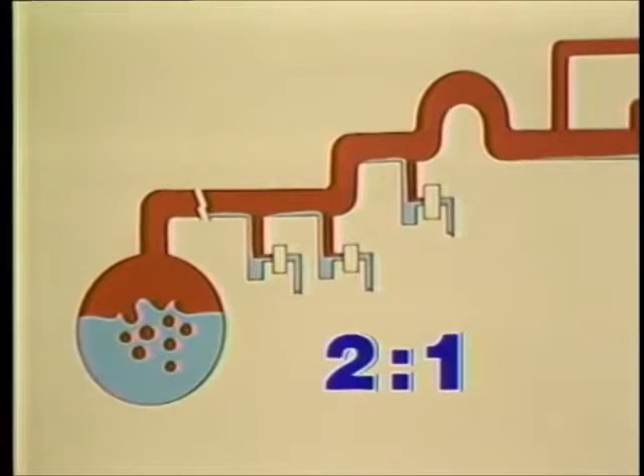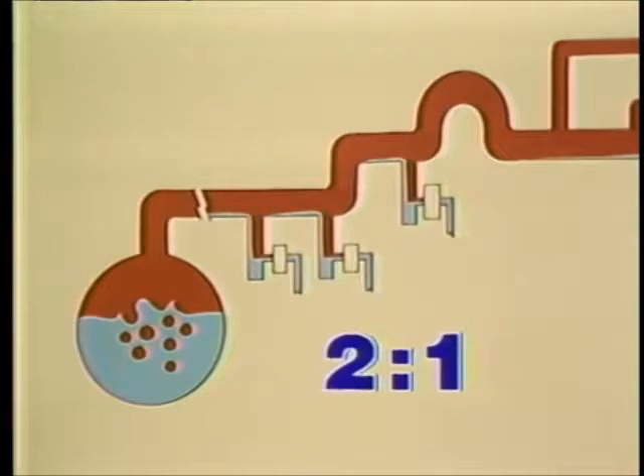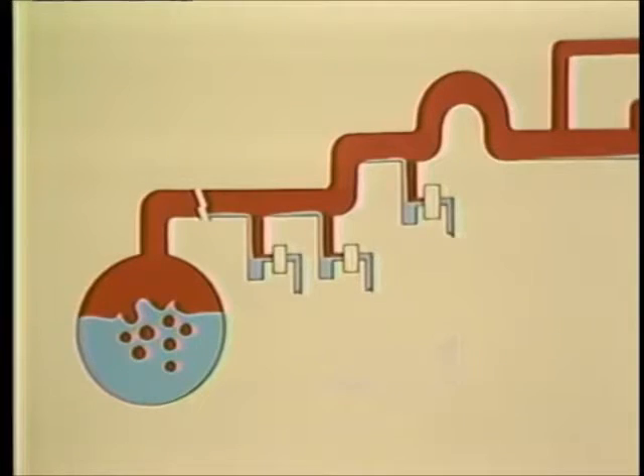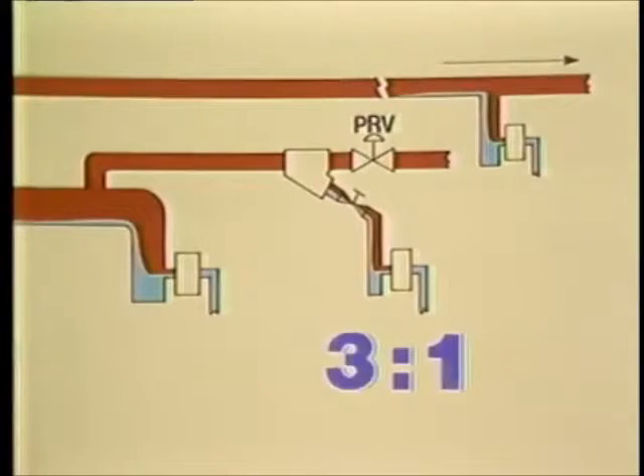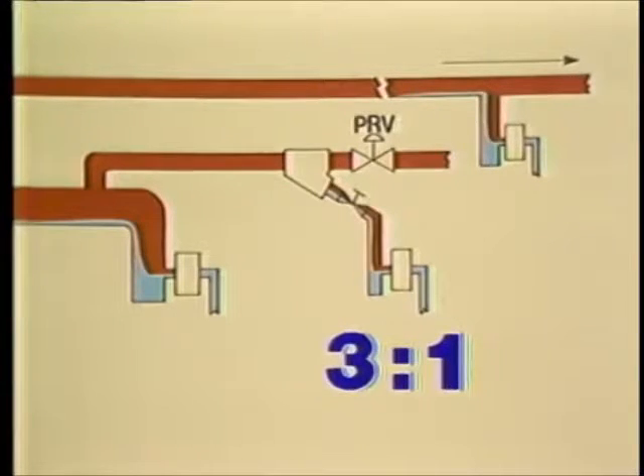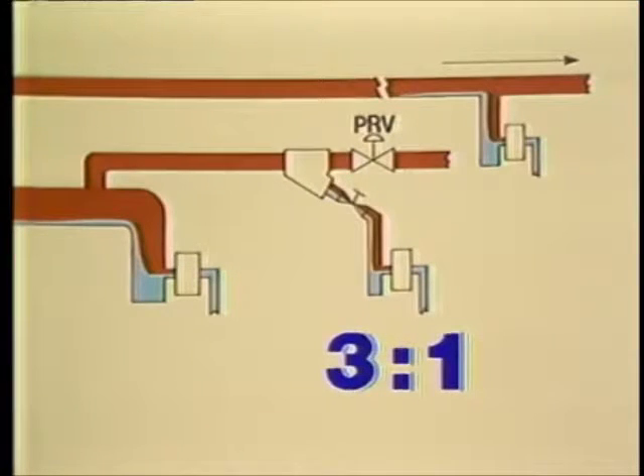Use a 2 to 1 safety factor for drip traps between the boiler and the end of the main. Use a 3 to 1 safety factor for the trap at the end of the main, and for traps ahead of shutoff valves, pressure reducing valves, and temperature control valves.